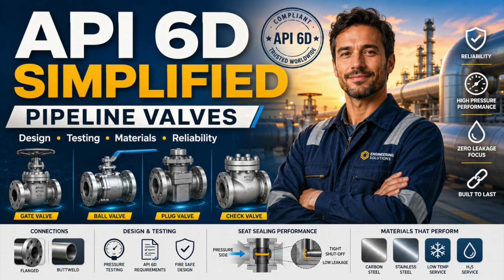Sour service also cannot be reduced to one note on the datasheet. Material grade matters. Heat treatment matters. Welding matters. Repair welding matters. Hard facing matters. Stem material matters. Bolting may matter. Hardness matters. A compliant base material can become non-compliant after uncontrolled fabrication or repair. That is why hardness control, welding procedure qualification, and manufacturing discipline are essential.